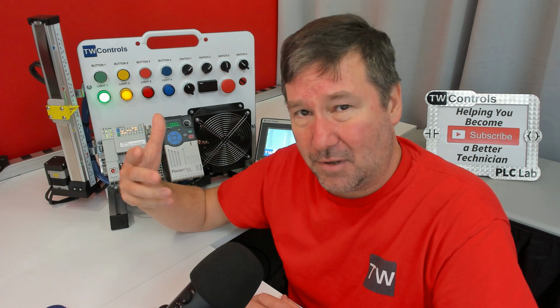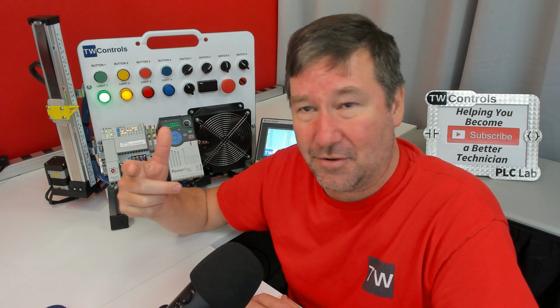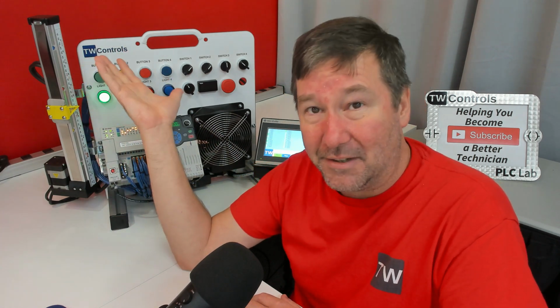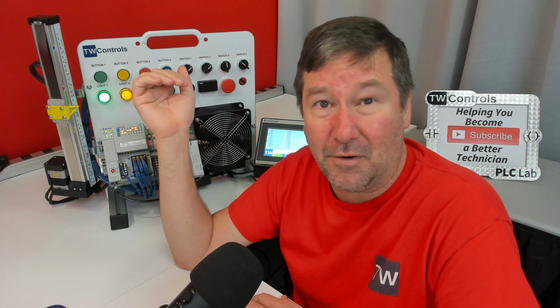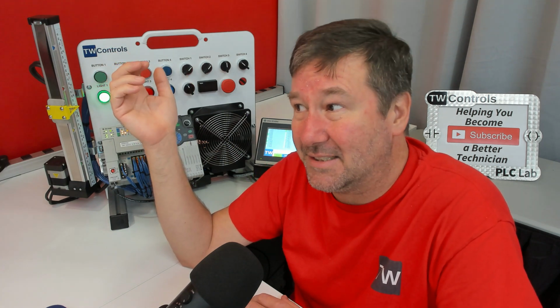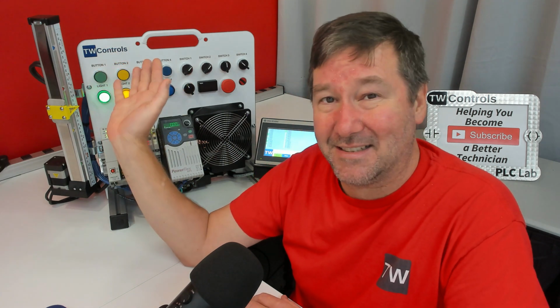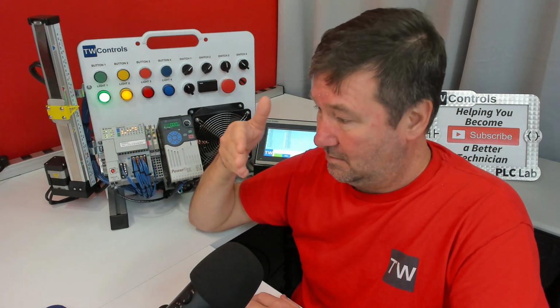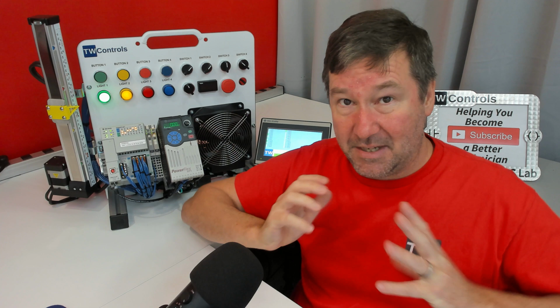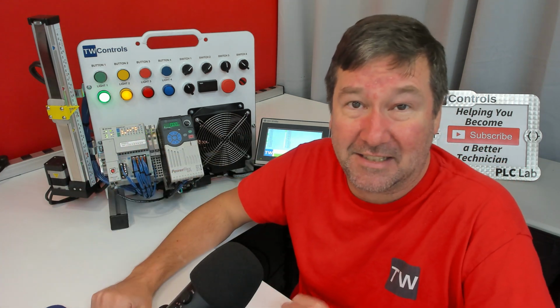Back up and think, are you sure you actually need a Kinetix drive? Because we could build a Kinetix trainer. Honestly, we have built them before. You don't see it for sale on our website because really, I think this is a smoother setup right here. So if you're doing a basic pick and place, grab a part here, move it over here, position this, then there are a lot of other options out there. Now, if we are doing a gearing application, or any type of following application, or any type of cam application, that's where the Kinetix comes in handy.